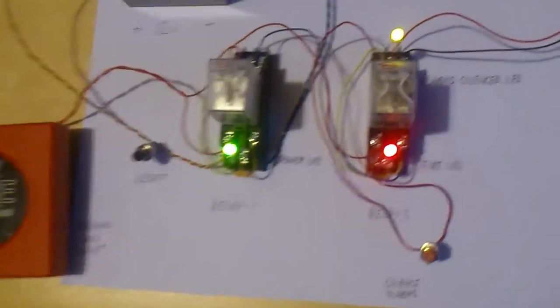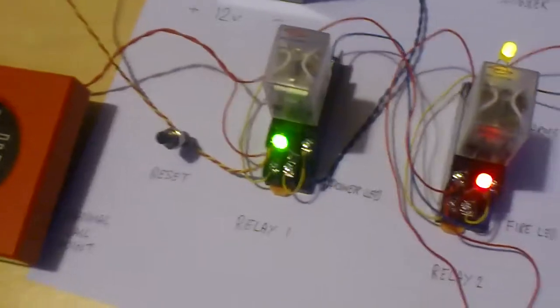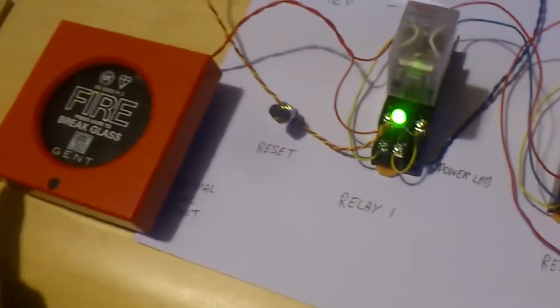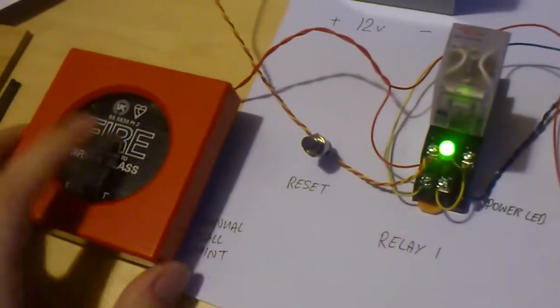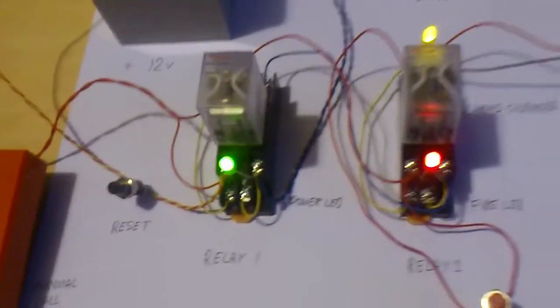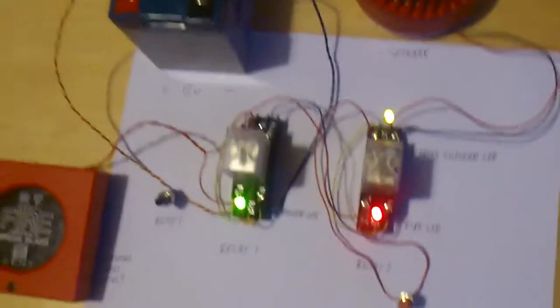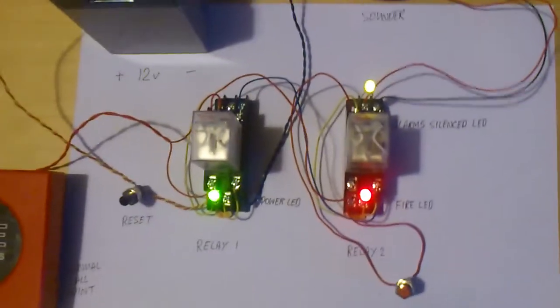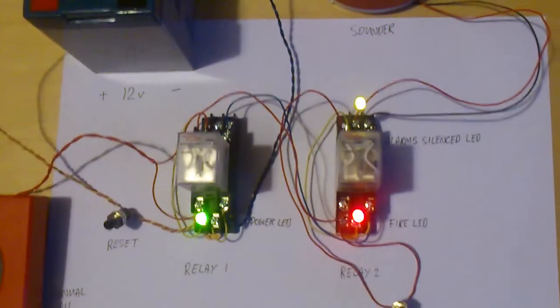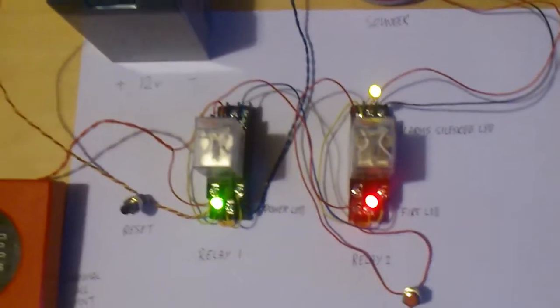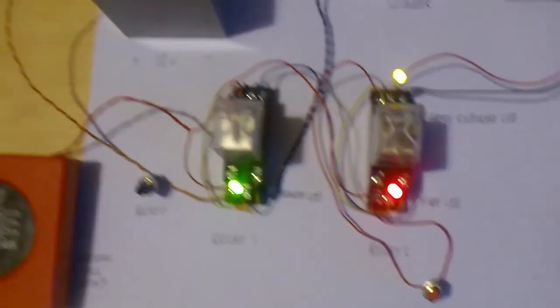Now, let's reset the call point by removing the key. The call point is now reset. It's not going to reset the system, though. You may have reset the call point, but you haven't reset the system because it still thinks there's a fire. It's still going to indicate fire with the LEDs.